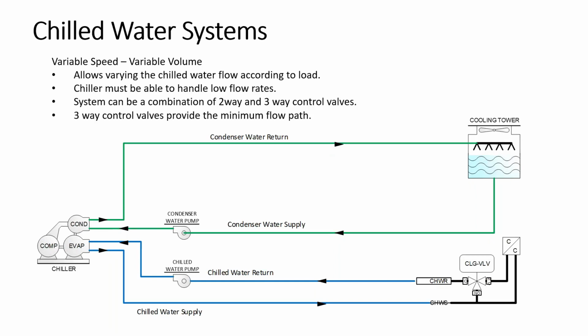So now we start getting into variable speed. We can have variable speed systems where you can vary the chilled water flow according to the load, but the chiller has to be able to handle it at low flow rates. So you can have a combination of two-way valves and three-way control valves. Three-way control valves provide the minimum flow path. I've actually seen buildings where they have one three-way control valve that was sized large enough to where it could provide the minimum flow to keep the chiller online. And so when it modulates, it gives the water a path to travel back to the chiller without interrupting it. Otherwise, if you had nothing but two-way valves, you would deadhead or block the pump, you would resist the flow of water and eventually get below the chiller's ability to stay online because the flow got so low.